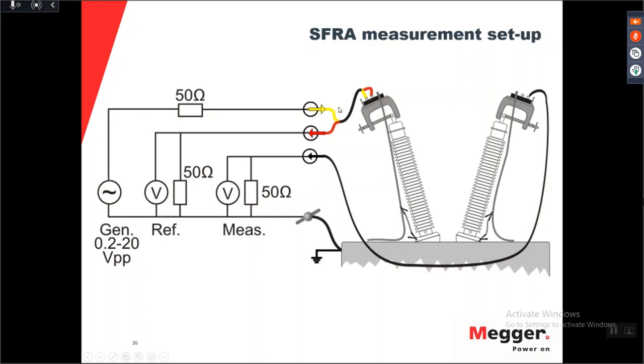So sometimes we have seen that the data sheets of different instruments are a little bit misleading, where they say they have this generation capability, and some talk about the voltage at the transformer end. So it is good to understand what you're comparing, so you compare the different traces with the correct foundation. So when you apply 10 volt here, you of course measure the applied voltage, so you have a reference. When we apply the voltage, it goes in through your transformer and it comes back through your circuit, and it has attenuated. So the measured voltage here, of course, is much lower. And then you measure how big that voltage is. And then you have the capability to look at this.